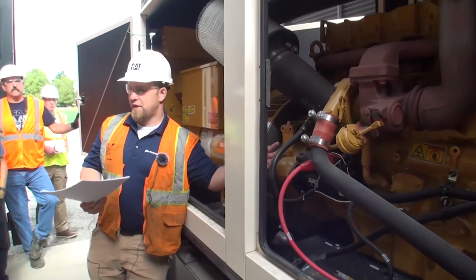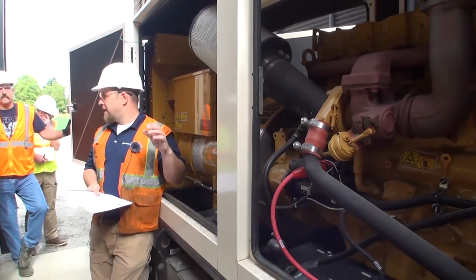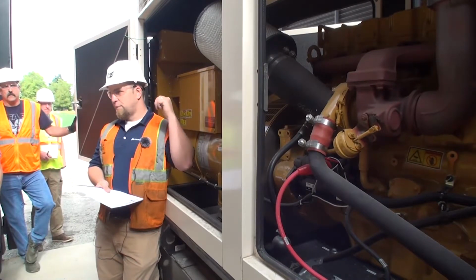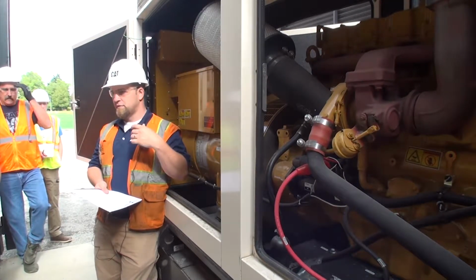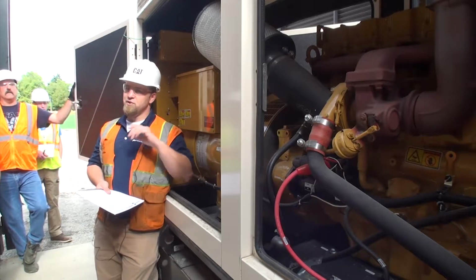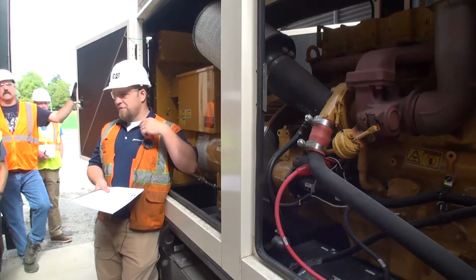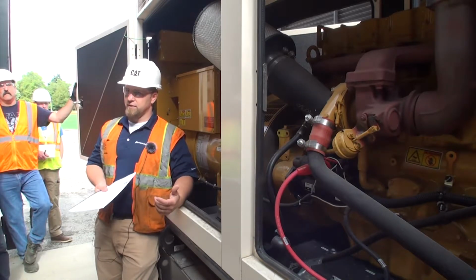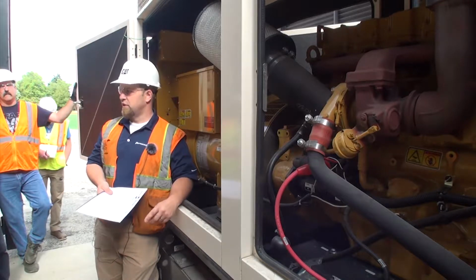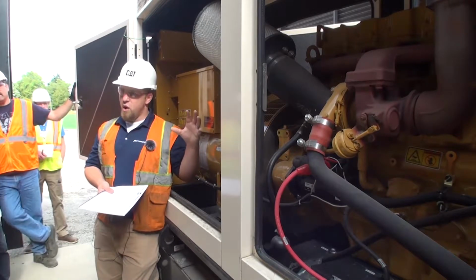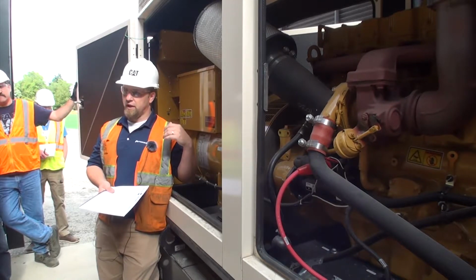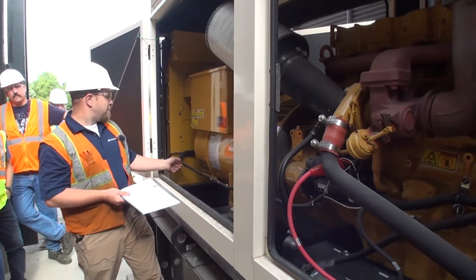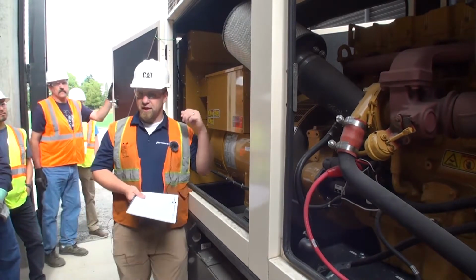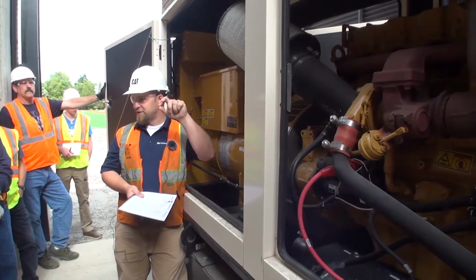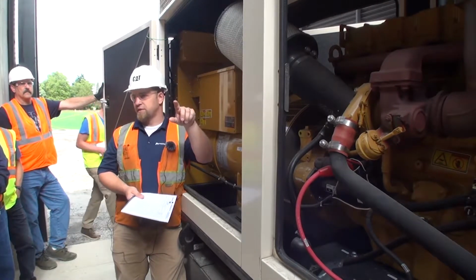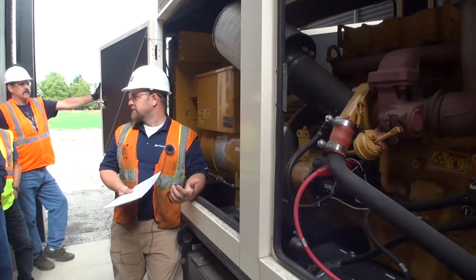You'll also notice when you have a low coolant alarm, you'll walk over here and this will be ice cold. I always say to do that, so if you get that alarm, you can call us and say, I took a picture, here's what the alarm was, I'll send it to the service department. Then we come out already knowing it's the block heater rather than driving out here, finding it's bad, driving back to get one, driving back again - a whole day for something we could fix in 2 hours. So take a picture of the alarm, and do a 1-2-3 check with someone on the phone: check that the breaker for the block heater, which is on the other side - just a 120 breaker panel - is reset, and make sure inside the building where it's fed from is all reset too. That saves you a service call.